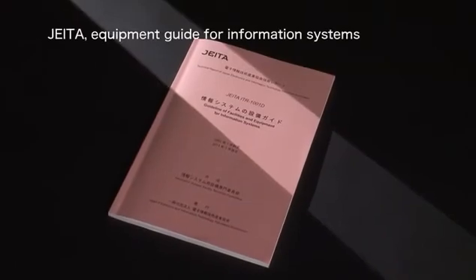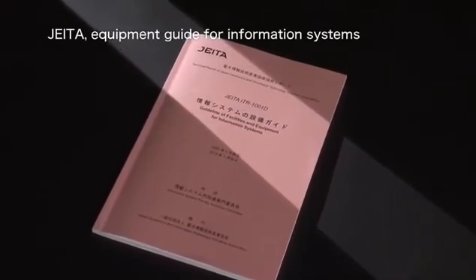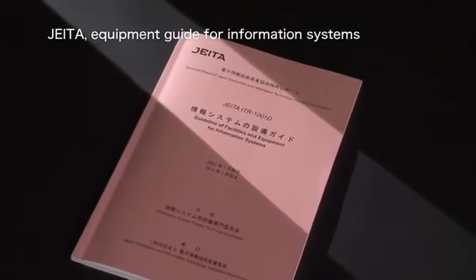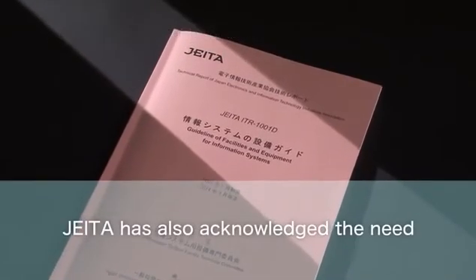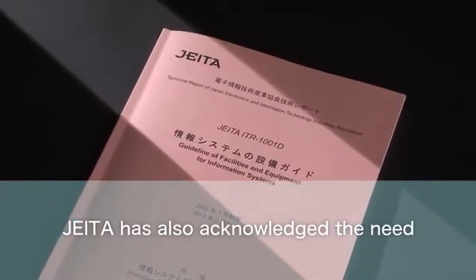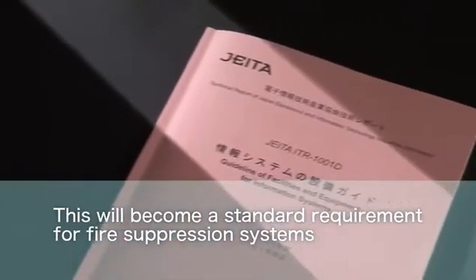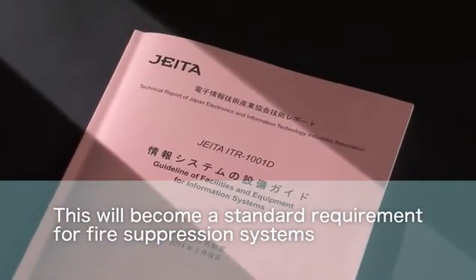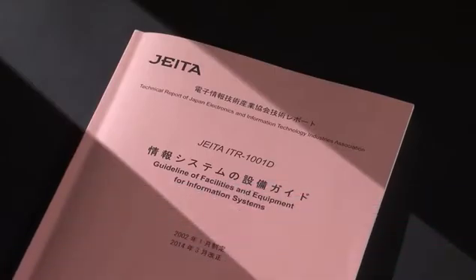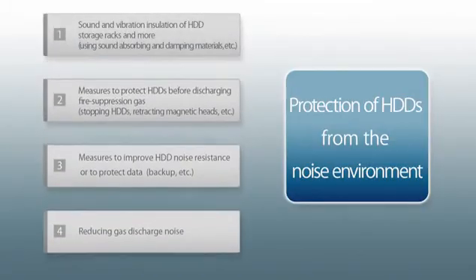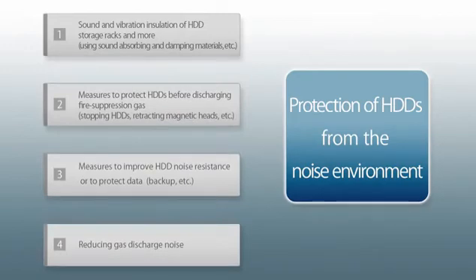The Japan Electronics and Information Technology Industries Association, an industry group promoting the IT and electronics industries and technology development, has pointed out the need for countermeasures to address this issue. And in the future, these will likely become a standard requirement for fire suppression systems. A comprehensive variety of measures are needed to protect hard disks from the acoustic environment. These may include protective measures such as sound and vibration insulation of storage racks, stopping hard disks before fire suppression agents are discharged, maintaining backups, and reducing gas discharge noise.